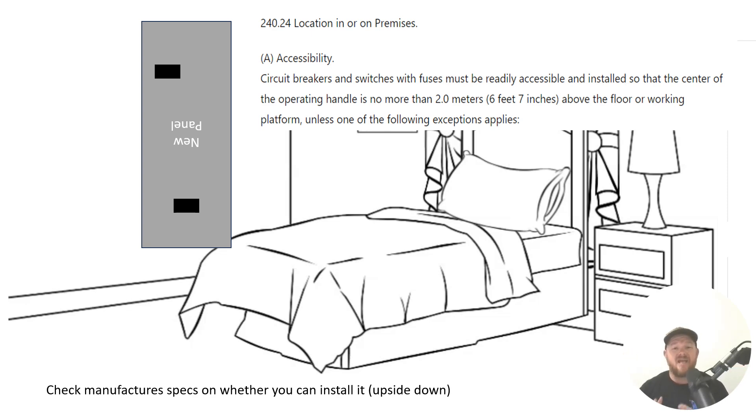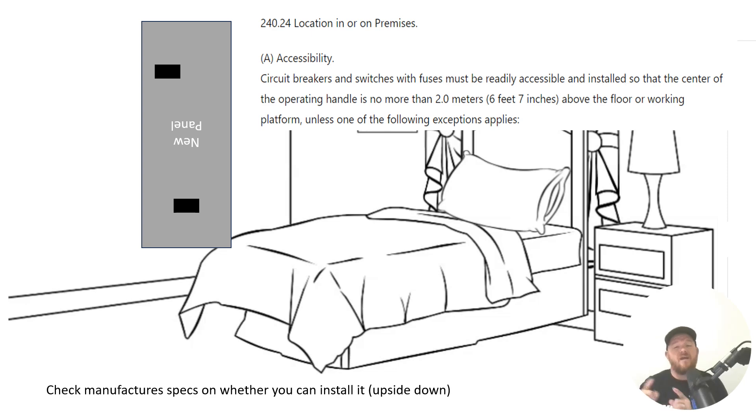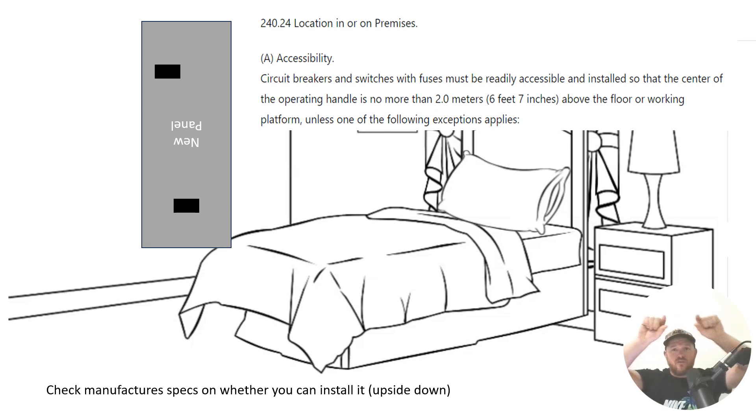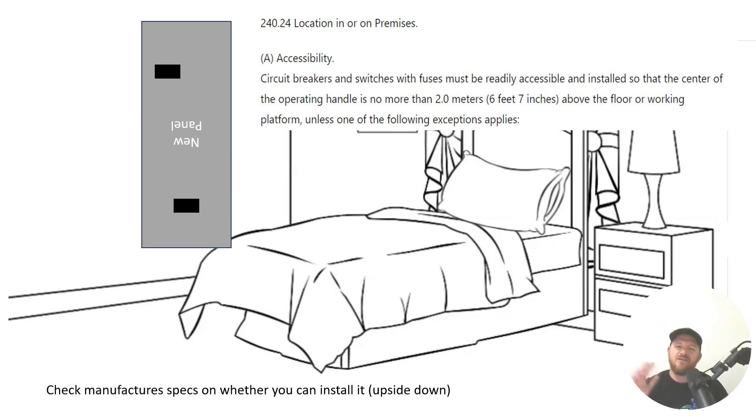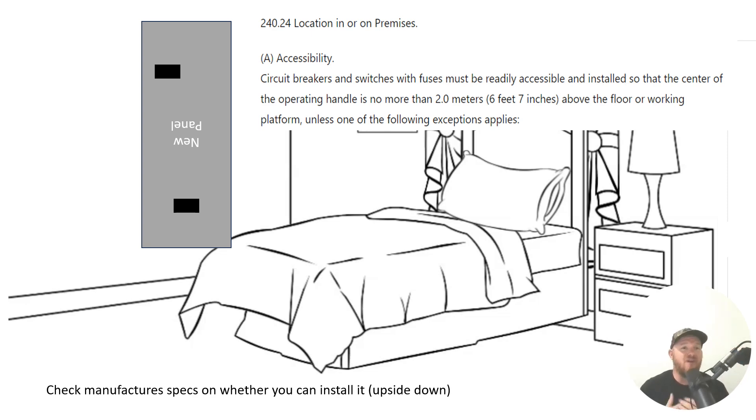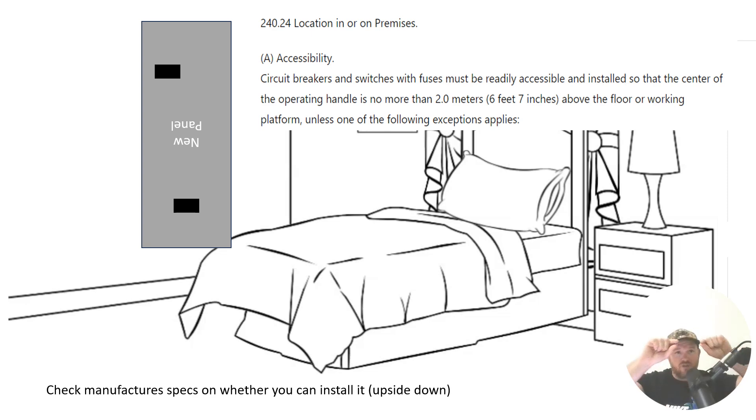So just keep that in mind. And in my opinion, like in this scenario today, if you flip that panel upside down and let's say you're not even using those unused spaces and you use all of these lower spaces closer to the main breaker and you're like, none of the breakers I've installed today are over six foot seven. If I'm your inspector, I'm going to say that includes also any of the available breaker spaces.